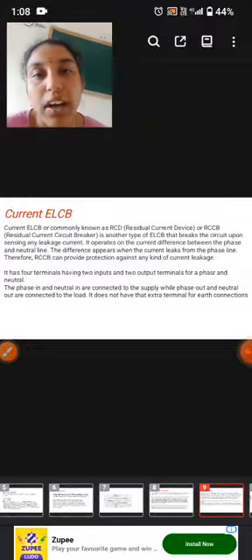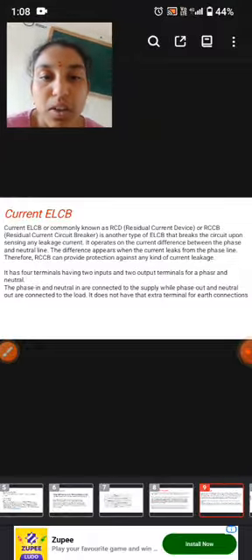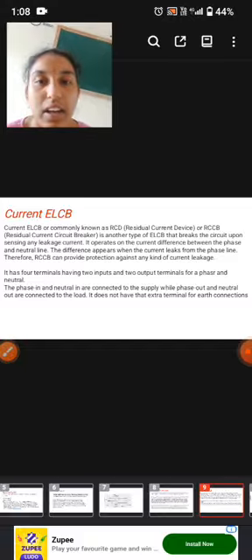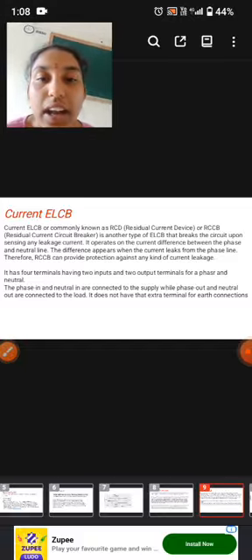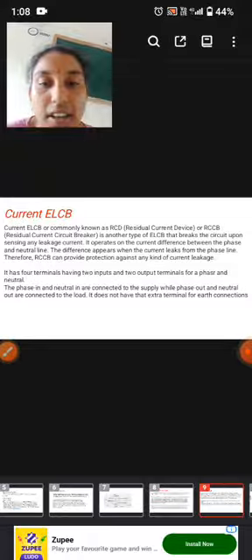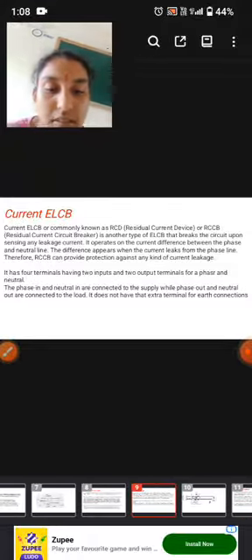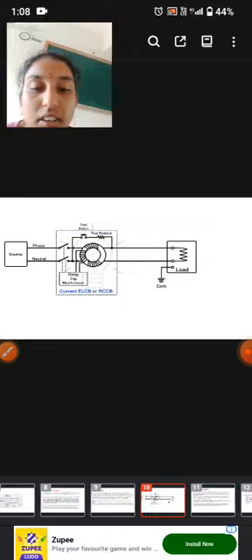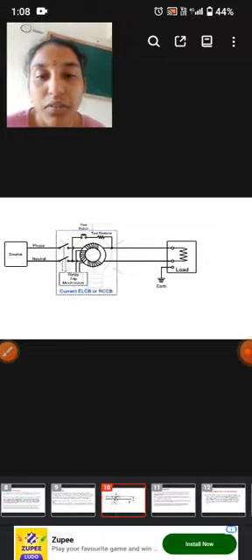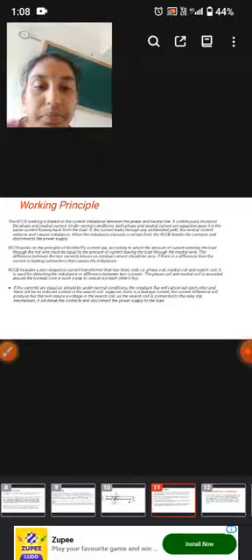It has four terminals, two inputs and two outputs, for a phase and a neutral. The phase in and neutral in are connected to the supply, and phase out and neutral out are connected to the load. It doesn't have an extra terminal for earth connections. And this is the diagram or connection of current ELCB.